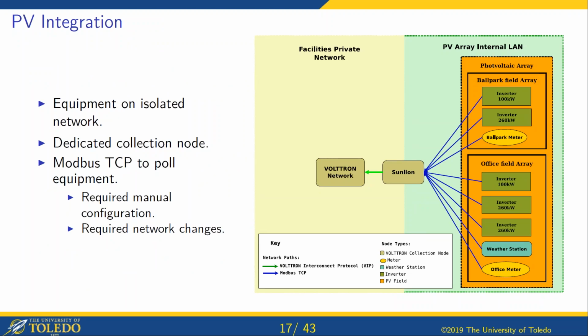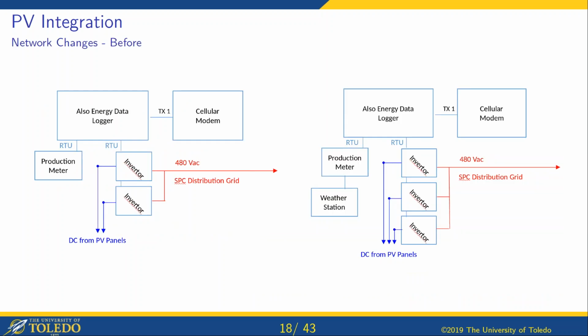So when we go to integrate the PV array, we had to actually make some changes to our network in order to bring it in. As I mentioned, this is actually under a power purchase agreement with another company. And so we did need to work with them. It has its own dedicated collection node, which sits out in the field near the PV array. And we were able to bring in a dark fiber that was already installed between the PV array and the buildings, which wasn't being used. As it looked when we got to it, the two arrays were completely separate. Each is communicating out with the SCADA provider that manages those arrays using a cell modem from the field.